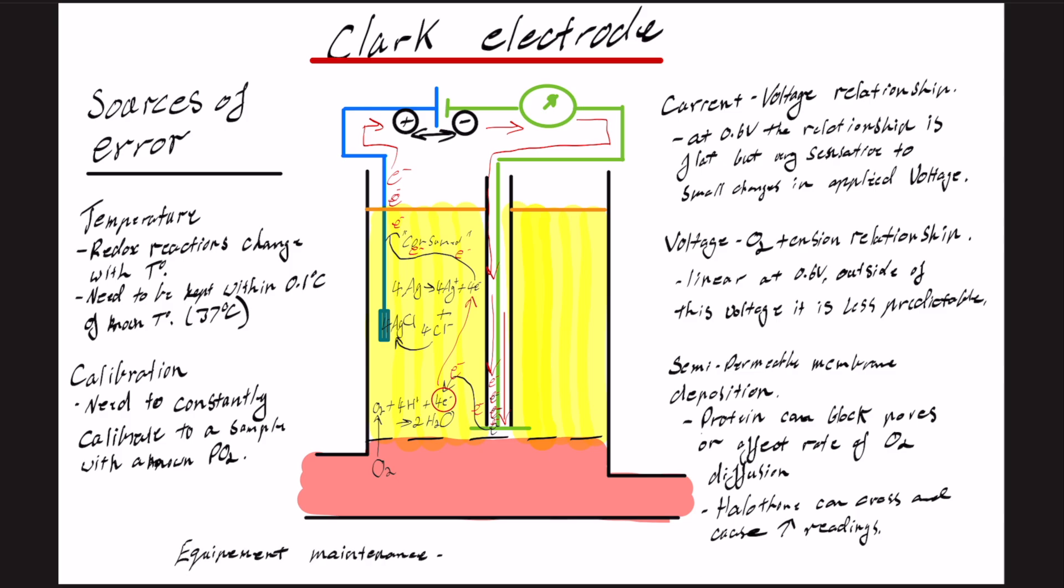You also can think of equipment maintenance issues. So you need your battery changes. You need the possibility of silver buildup on the platinum cathode as well, because remember the platinum cathode is negative, while the silver is charged positive, and slowly silver can actually disintegrate off the anode and then settle and accumulate on the cathode.